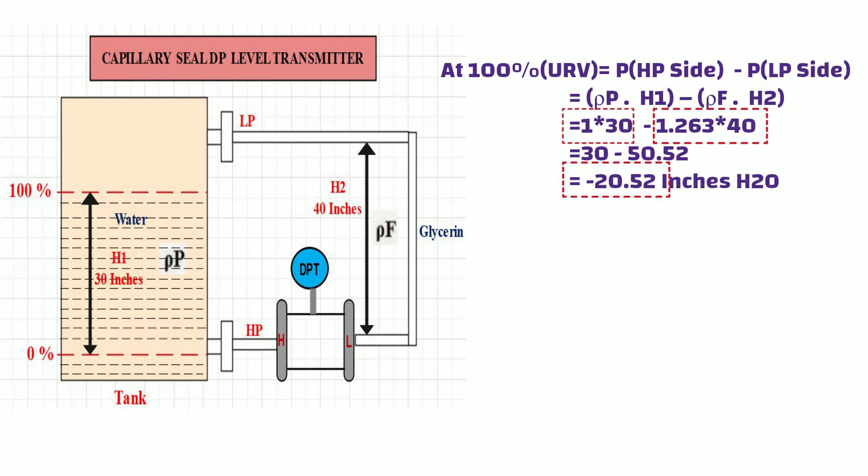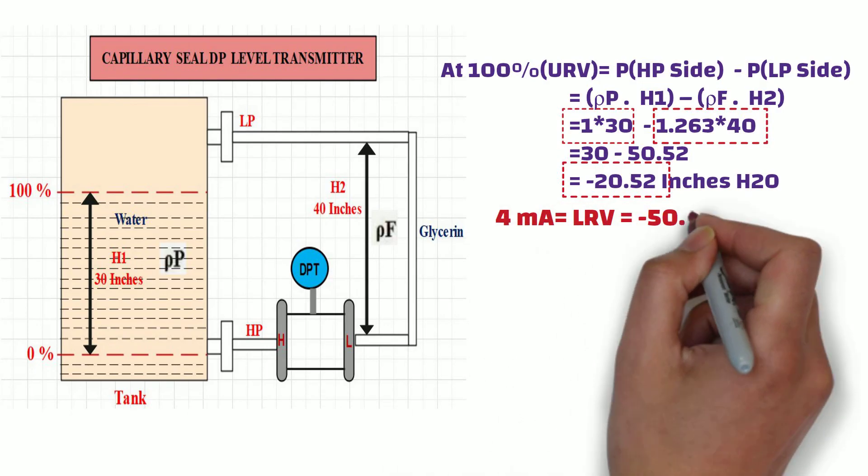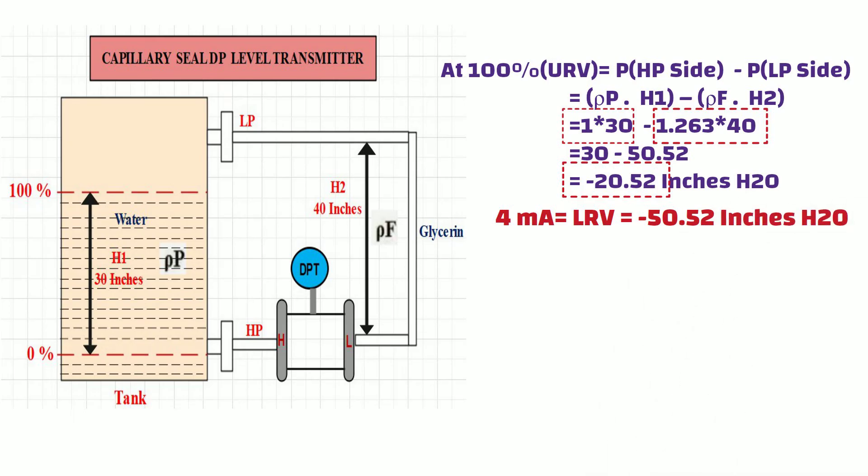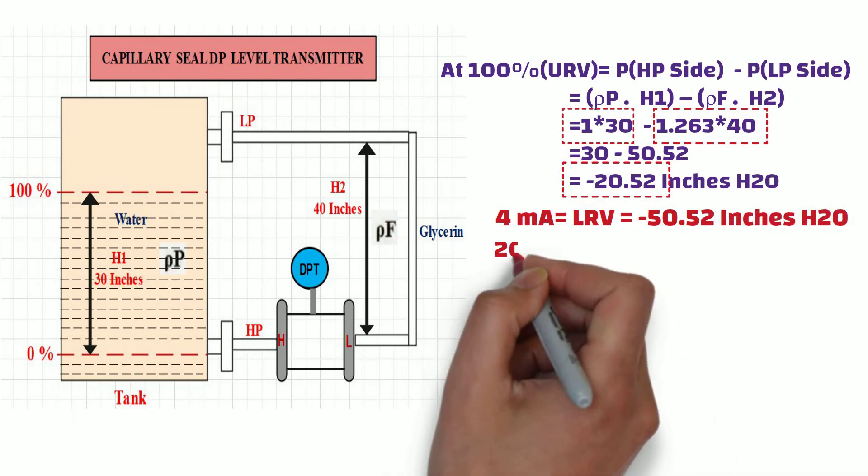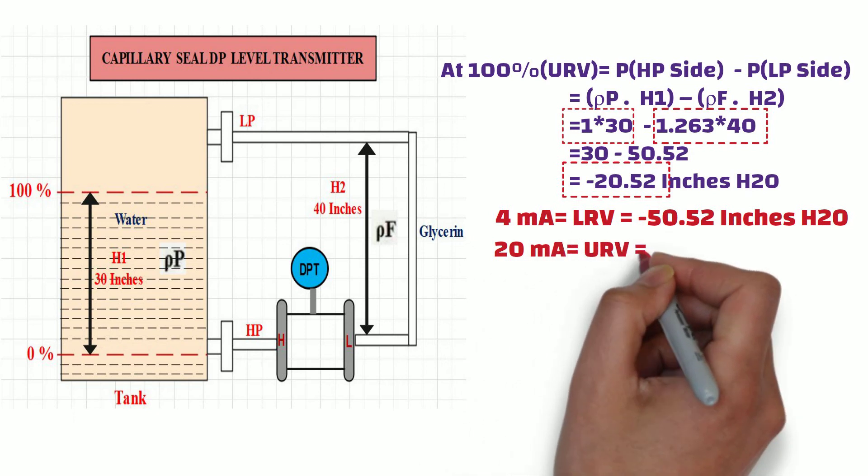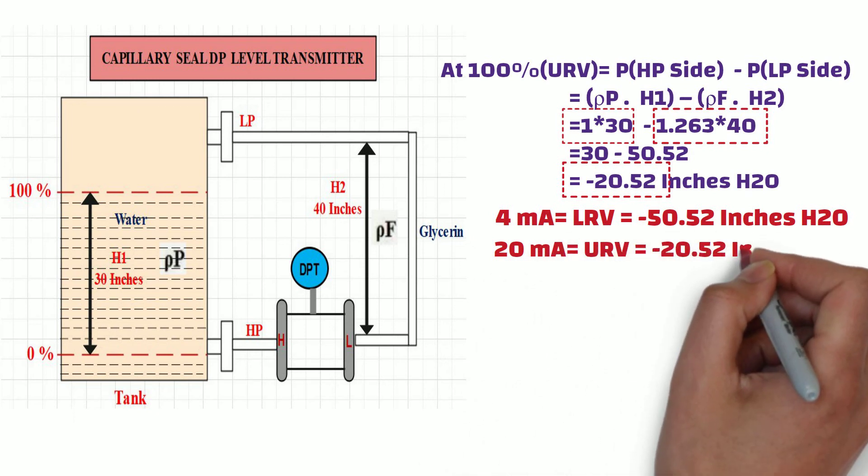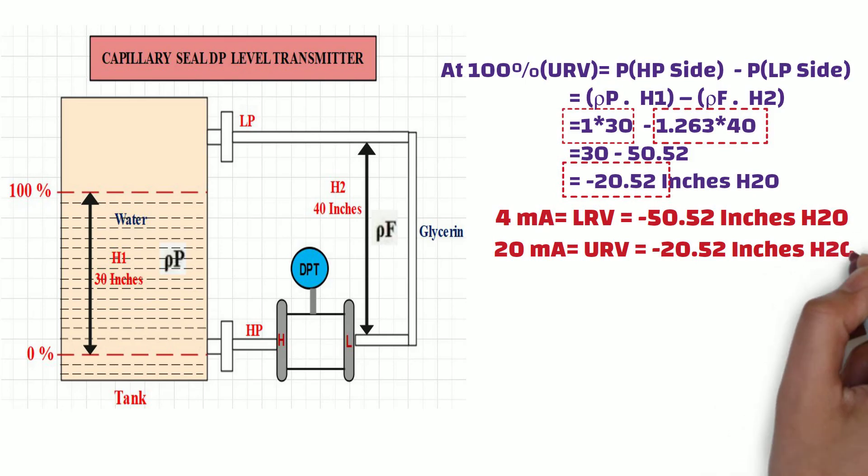So in this example, the DP transmitter gives 4 mA output when differential pressure is minus 50.52 inches H2O, and the DP transmitter gives 20 mA output when differential pressure is minus 20.52 inches H2O.